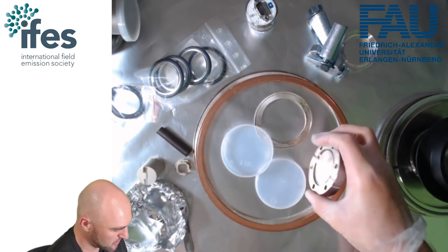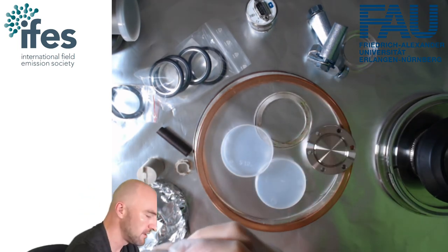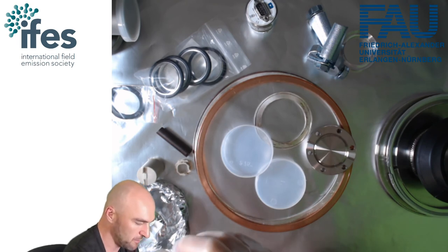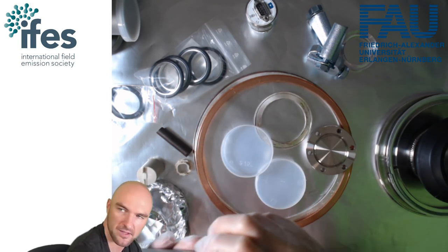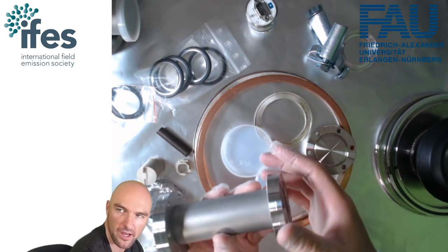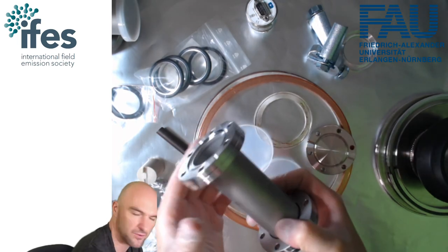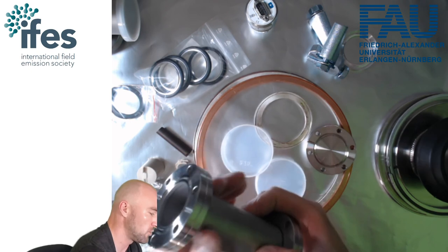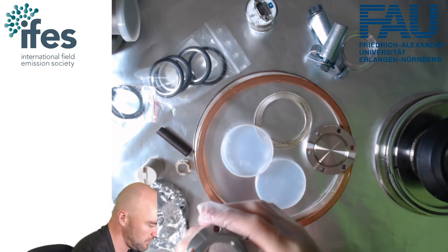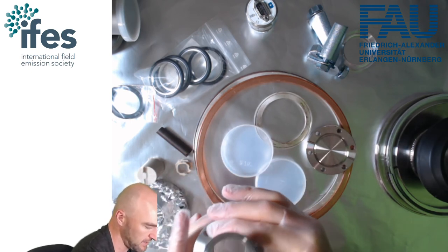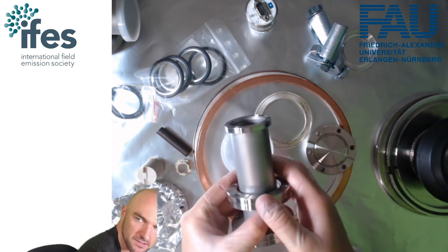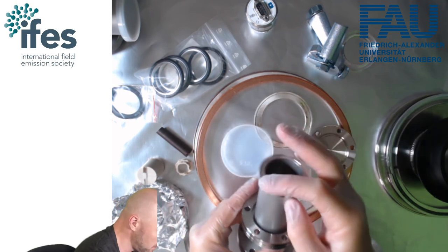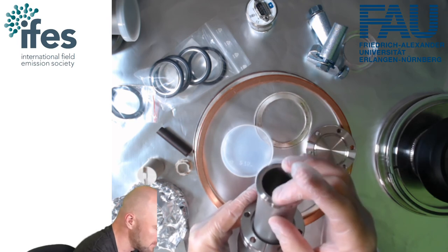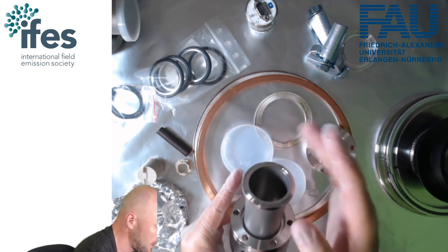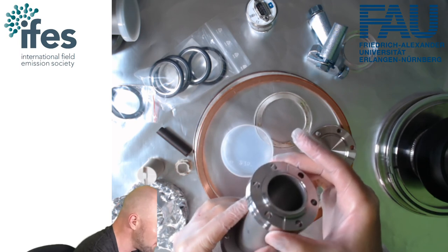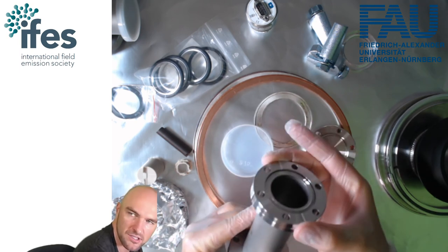So in terms of flange types, what do we have? I think we have the option to have rotatable and non-rotatable flanges. So if you know beforehand what orientation you want to have, it's always good to have non-rotatable flanges, because if you have a rotatable flange, the flange slides to the back, and it exposes the knife edge. So it becomes pretty easy to damage the knife edge. So if I can, I always design non-rotatable flanges, but sometimes you just need a rotatable flange.